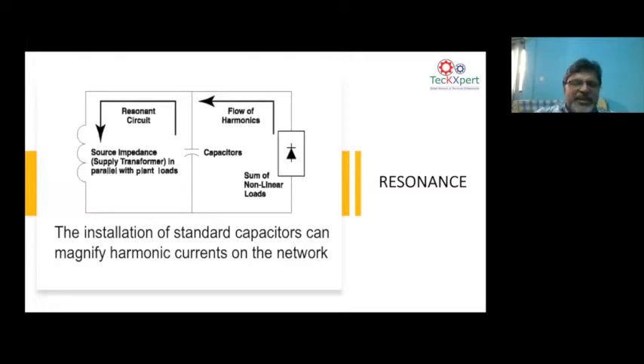Now here in this equivalent diagram, we are showing a harmonic current source. There is a plain capacitor bank in the system. This capacitor need not be a plain capacitor. It can also be the capacitance of your network. Your cables have capacitance. Your whole system has both capacitance and inductance. Even a transformer has interturn capacitance. For a cable, the capacitance from phase to ground is also there. So the capacitance is the sum of all the capacitances. It need not be the standard capacitor that you add for power factor correction.